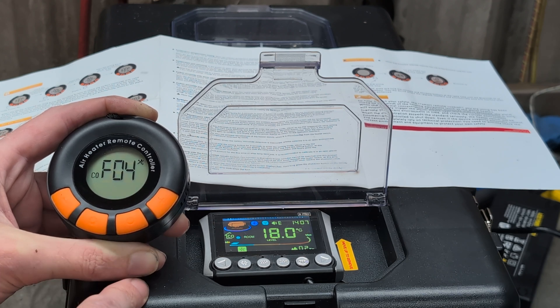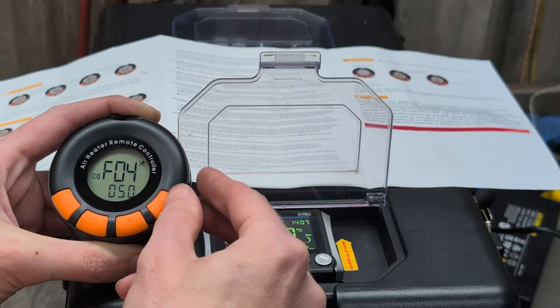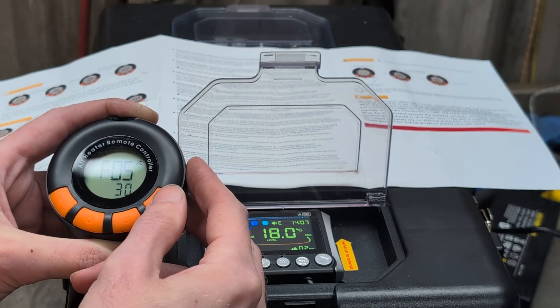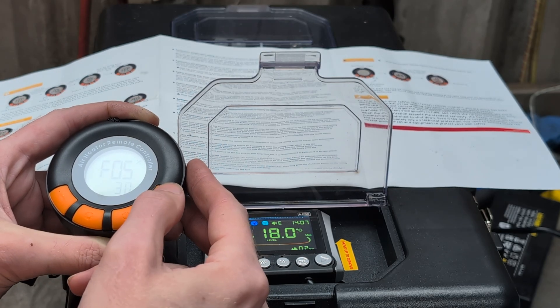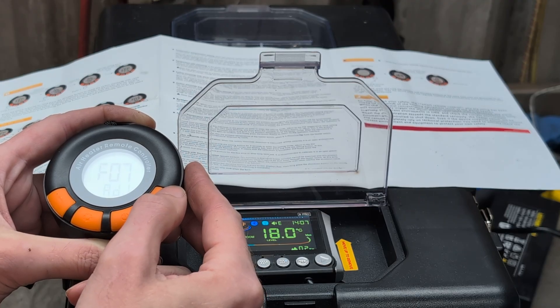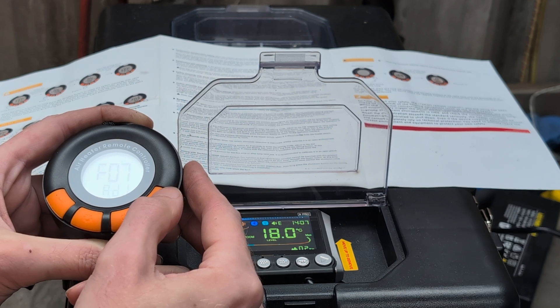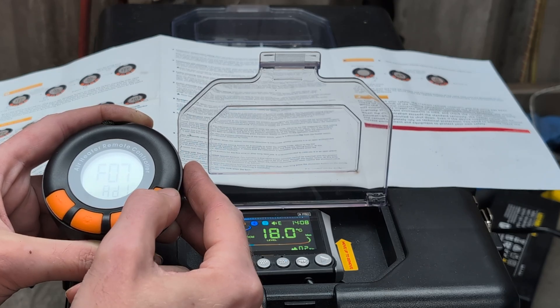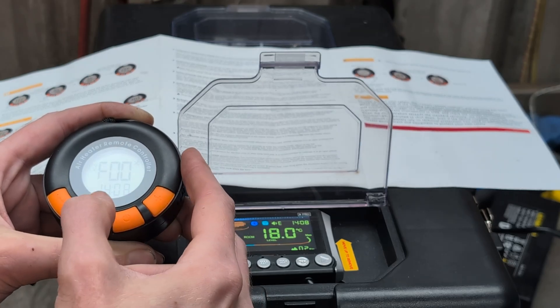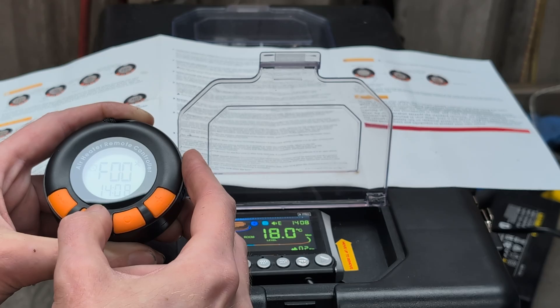Let's set the cutoff to 50 parts per million, because basically you don't want any carbon monoxide inside. F5 is the one we just set. F6 is the temperature value setting interface — not sure what that one is. F7 is the backlight. And then there's the carbon monoxide calibration setting, and F7 also tells you the firmware version. That's us back to the start.